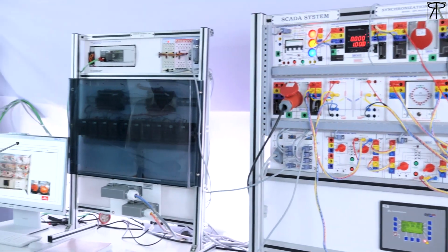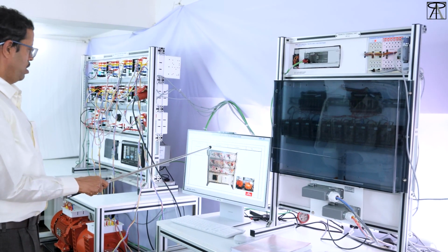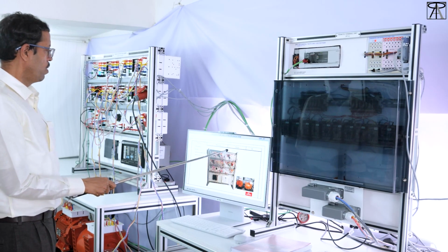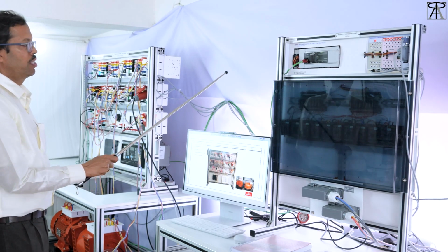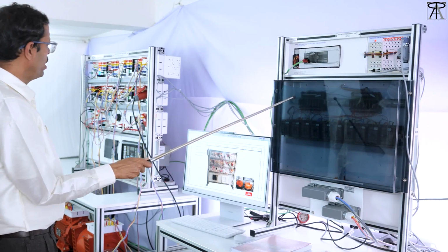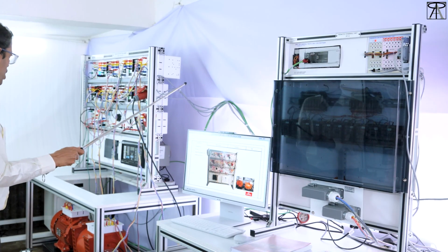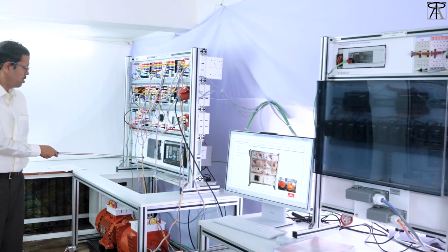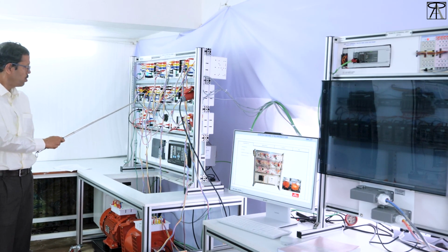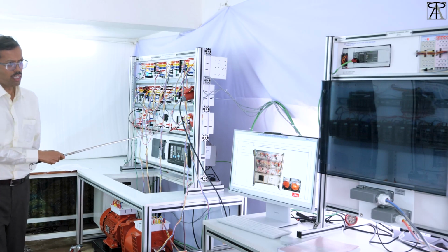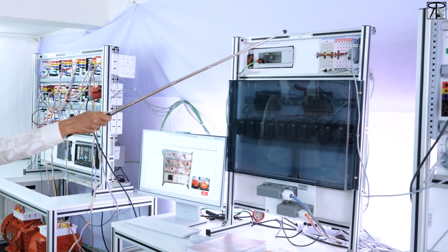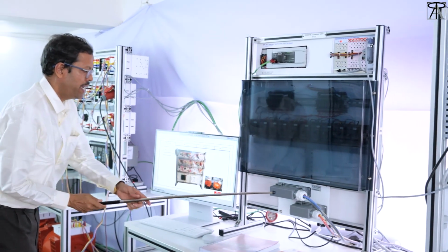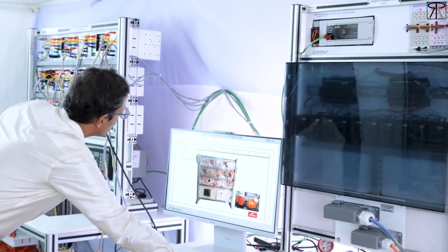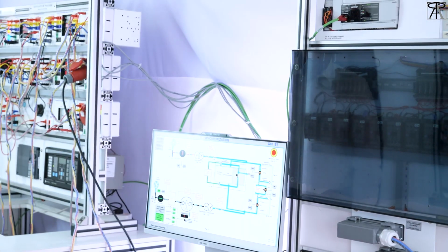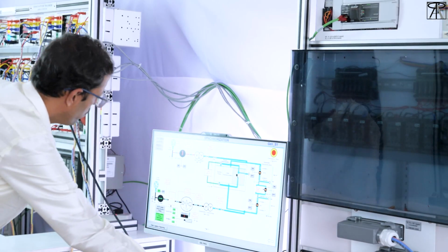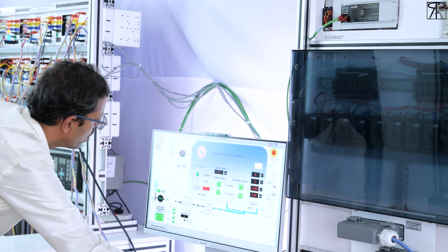Now we are using the generation screen in the SCADA software. We can make the synchronization, the first experiment. We have used a common remote terminal unit for synchronization and generation. This is for the generation trainer, used as one input parameter for synchronization. The other parameter we have used for the grid. Now we can make the synchronization using touch or using the mouse. Synchronization will come, and generation control you can start.